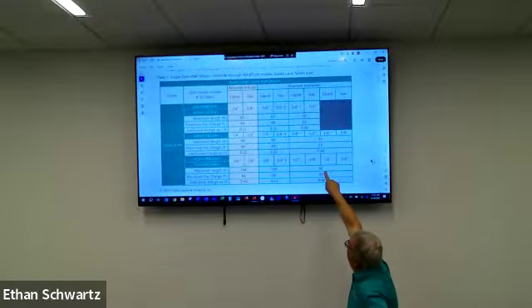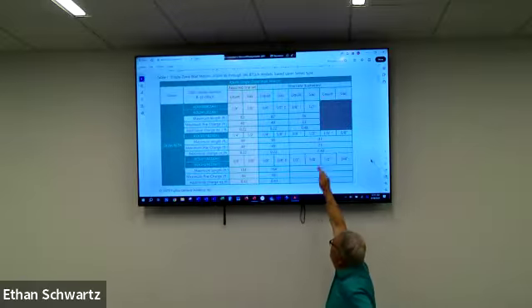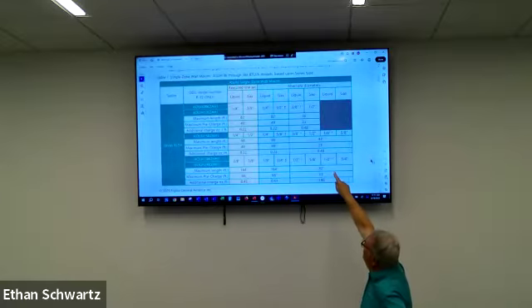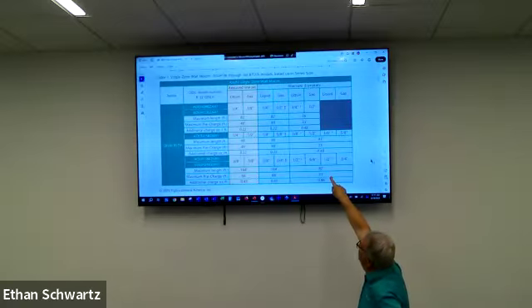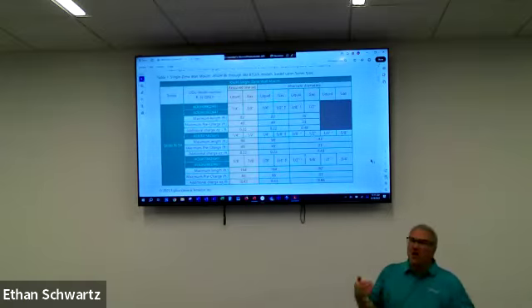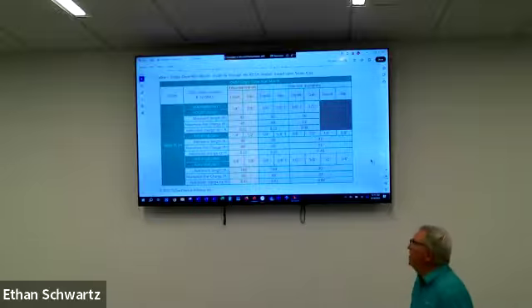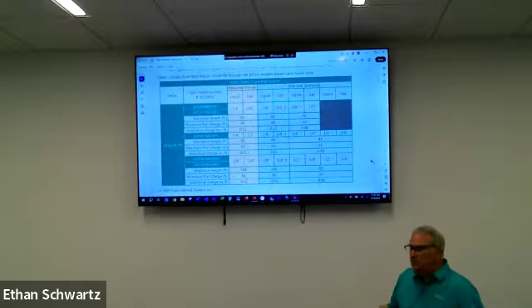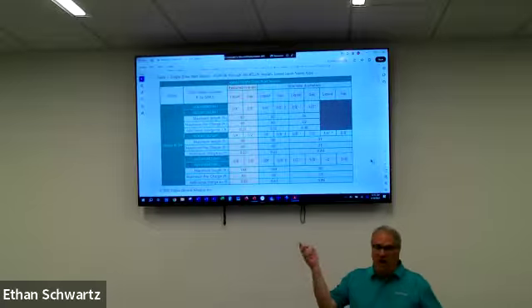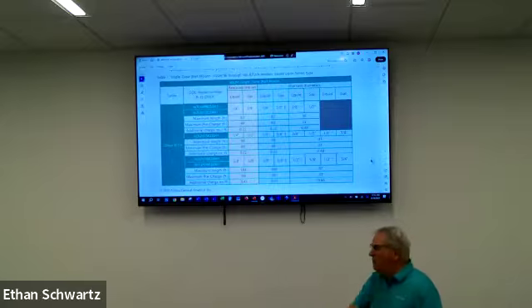Well, if that line is 23 feet or less, then you don't have to do anything. But if you are running longer than that, because the application's existing line is longer, then you're going to have to add 0.48 ounces per foot of additional line set. Make sense? For me, being 13 years with Fujitsu, that was huge, because it was always, no, rip it out, do it again, or I've got this existing line set, not happy with the previous company, or whatever the case is.